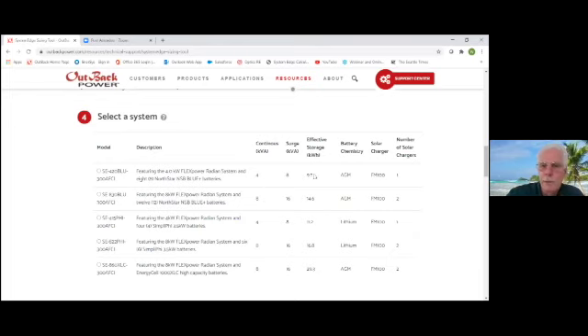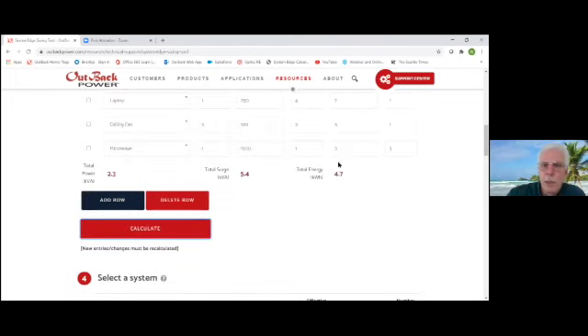And we're showing the surge, and here's the effective storage. Now here's another thing that we do - we don't use the nameplate storage. Like on an AGM battery, we spec it as 50% depth of discharge. When you see the SimpliPhi batteries, this number is based on 80% depth of discharge, because that's what they recommend for the 10-year warranty. So this number here comes from up on the table over here.